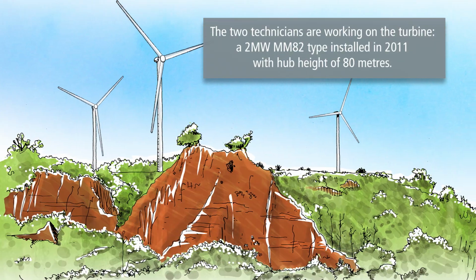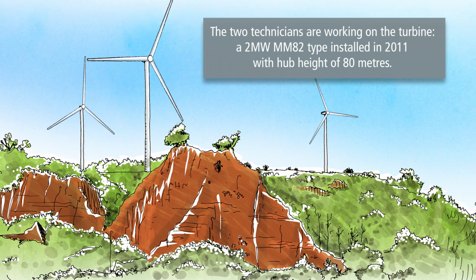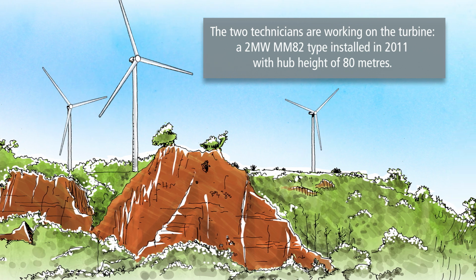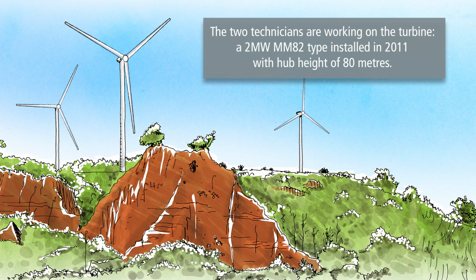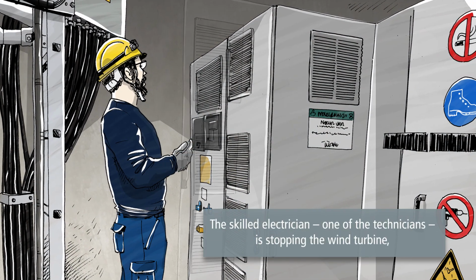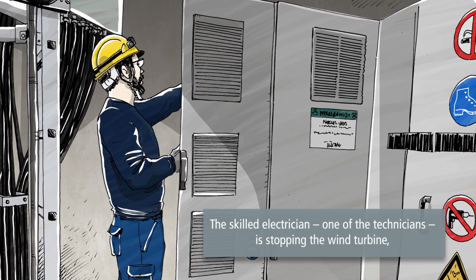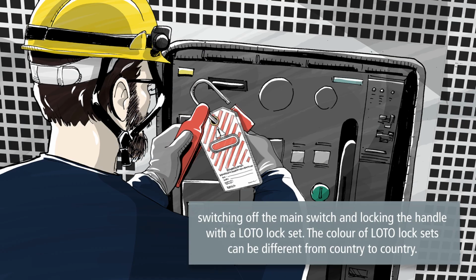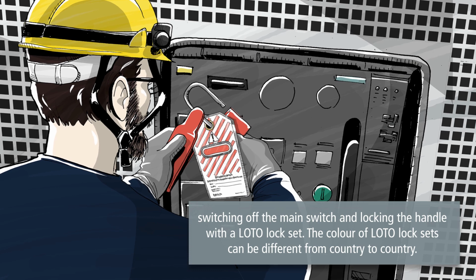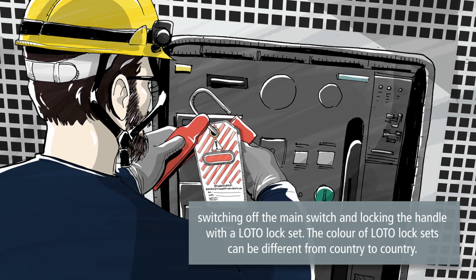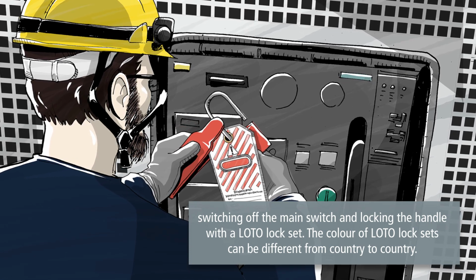The two technicians are working on the turbine, a 2 megawatt MM82 type installed in 2011 with hub height of 80 meters. The skilled electrician, one of the technicians, is stopping the wind turbine, switching off the main switch and locking the handle with a LOTO lock set. The color of LOTO lock sets can be different from country to country.